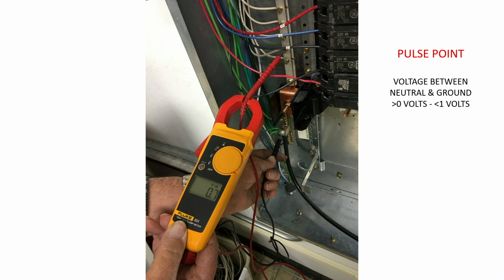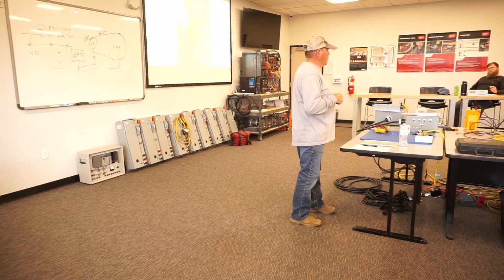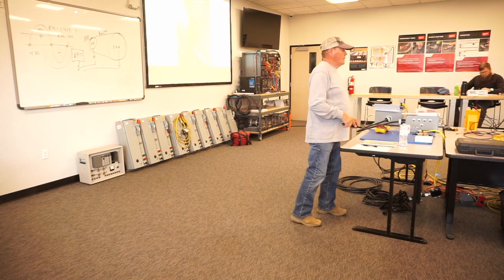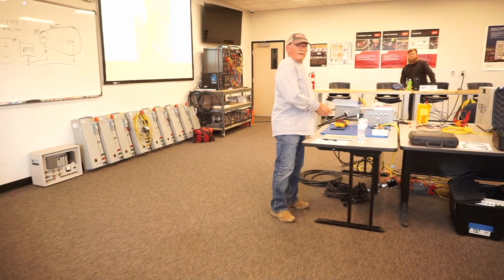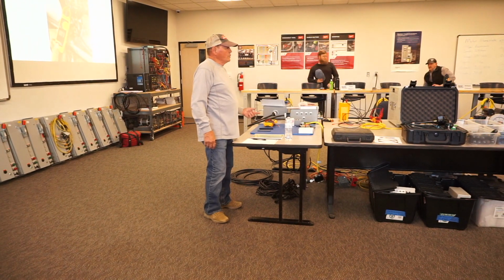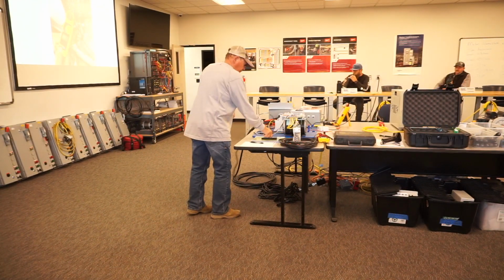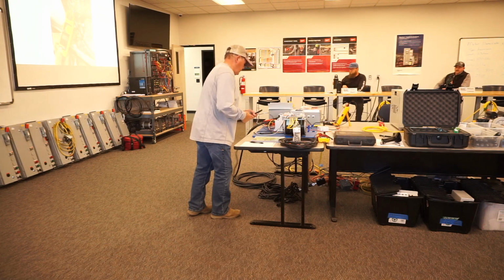What's the voltage reading between ground and neutral? And we're going to go downstairs to the solar room where there's a ground rod driven. We're going to measure that ground rod, and then we're going to disconnect it, and you can read the voltage between that conductor and the ground rod. So let's take a break, and then when we reassemble, we'll go down there and we'll play some games with that brand new ground rod they drove down there. Because our goal is, okay, moving onward before we fire up this equipment over here.